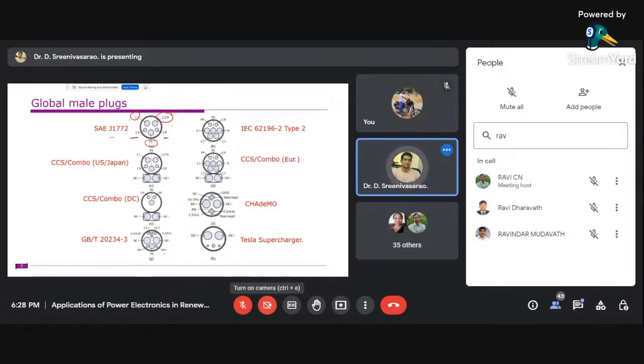So this is for single phase, and the same thing for 3-phase. You can see here L1, L2 and L3, these are for 3-phase. Again these three are used to get the data, and this is the neutral wire, and this is the ground one. And the PP and CP are the control pilot pins, the pilot switches used to get information about the charge, how much percentage it is charged, and whether it is properly connected or not. So that kind of information is provided.